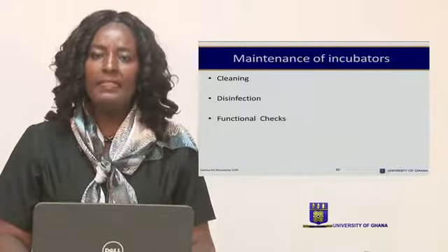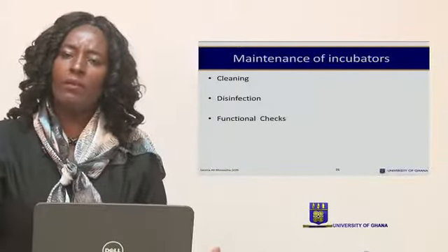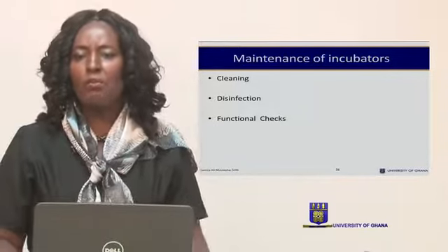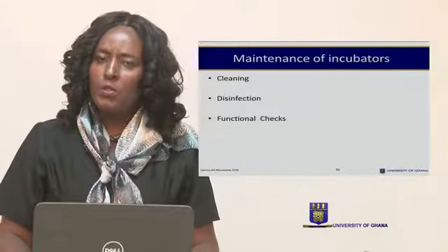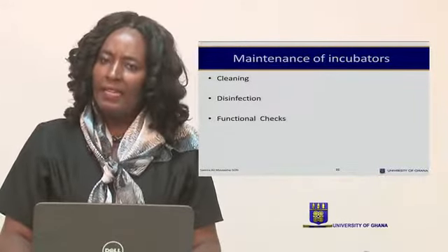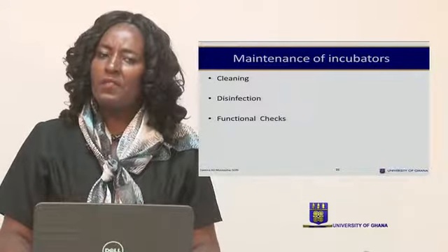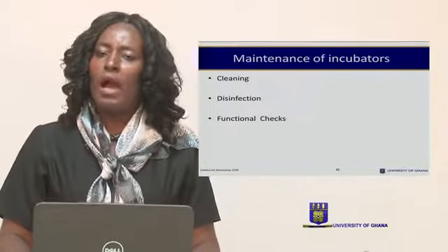We have to clean the incubator with sterile or distilled water, and it also needs to be disinfected, so we can use Savlon that should be diluted, that we use to clean, and after that we further clean it with the sterile water, because if the disinfectant is too strong, it can predispose the newborn to apneic attacks.